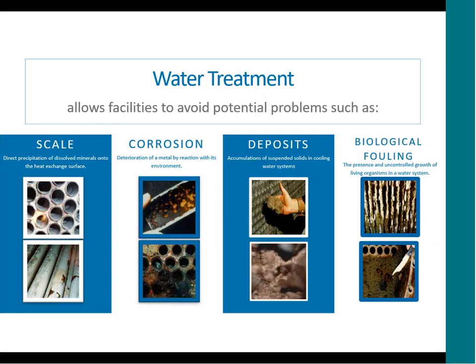The top picture, it's sticky. It can impede airflow and water flow. Your system's not going to operate as efficiently as it should. You can have biofilm. The bottom picture. The problem with biofilm is that it's also an excellent insulator. Again, we're trying to transfer heat, so we don't want anything that's going to insulate. Biofilm is more insulating than scale. So we don't want anything that would inhibit the efficiency of our system. And another potential problem with cooling tower systems is that they have the potential for pathogenic bacteria to proliferate in the system. So properly treating a cooling tower system can also be a matter of public health.